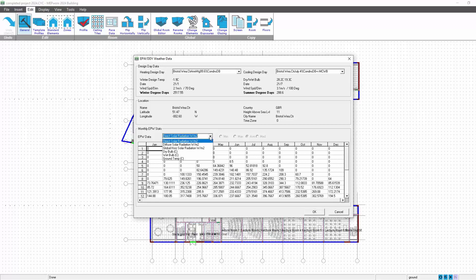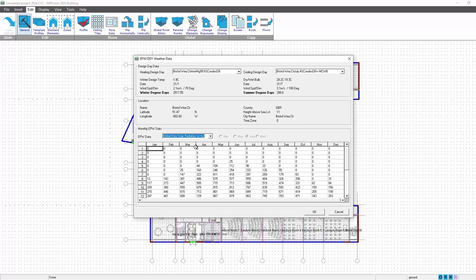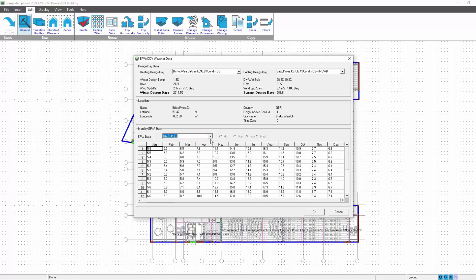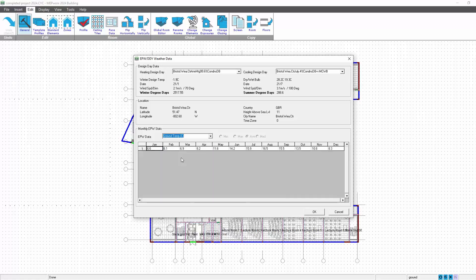Also, you can view the diffuse solar radiation, the global horizontal solar radiation, the dry bulb temperatures, the wet bulb temperatures. Another new thing we've introduced is the ground temperatures. For the heat loss calculations, depending on the month of selection, it will look at these ground temperatures and apply the delta T in accordance with the difference between the ground temperature specified here and the room temperature that you're currently defining.